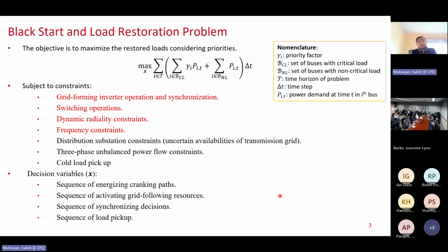And there are a certain number of constraints for this problem, out of which I am focusing only on 4 important constraints that are shown in red. So the first constraint is grid forming inverter operation and synchronization. How to model them, I will discuss in the next slide. And then the switching constraint, dynamic radiality constraint, and frequency constraint. And the output or the decision of this problem is the sequence of energizing cranking paths. It could be a sequence of activating grid following resources, sequence of synchronizing decisions, and sequence of load pickup.